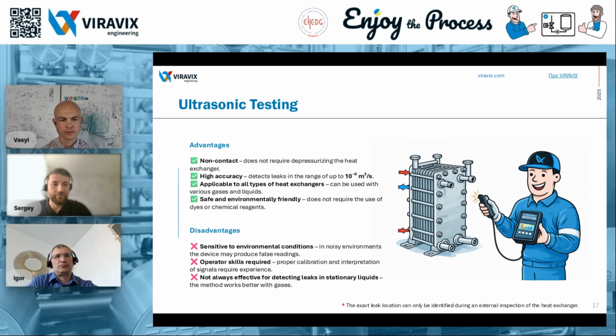If there is microdamage, the device detects surface irregularities. The ultrasonic wave reflects differently when the surface is not intact. When a leak is detected, the device produces both an audible and visual signal. The exact location of the defect can then be identified. This means that the defect can be located during an external inspection of the heat exchanger.